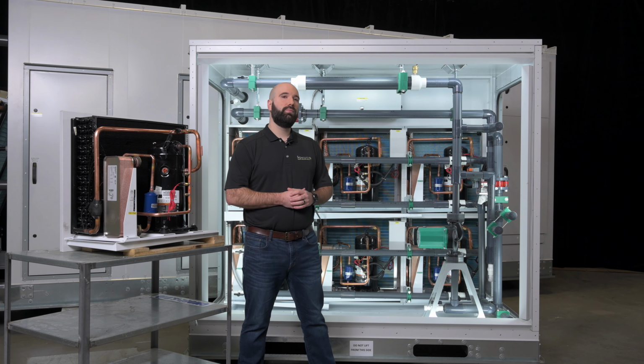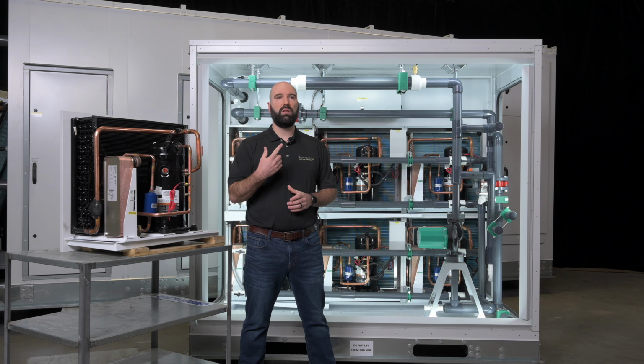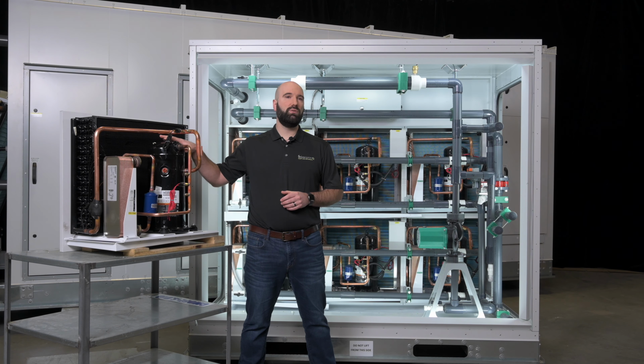The built-in pump and mixing valves allow us to circulate that water for cooling and reheat flow, as well as control and modulate between the reheat coil and the dry cooler for heat rejection. Each one of these pods is using electromechanical speed or capacity reduction technology. These are the Copeland ZPS 2-stage compressors. That electromechanical capacity reduction is very reliable, very robust, and in low speed mode, these are mostly sensible pods. And then in full speed or full capacity, we add in the latent cooling. So the sensible cooling being the air conditioning part, and the latent cooling being the dehumidification.